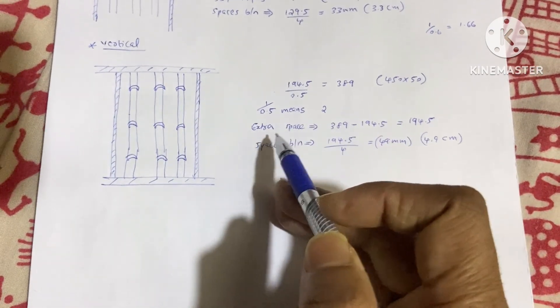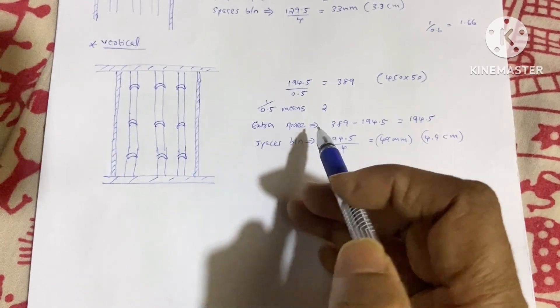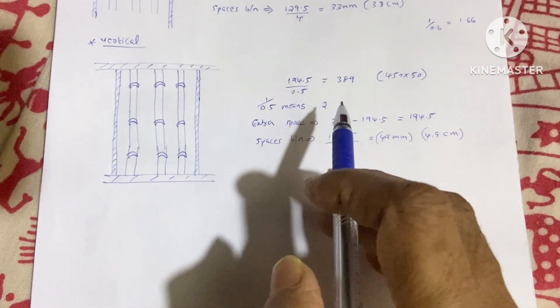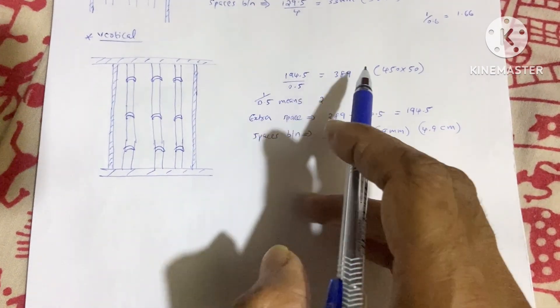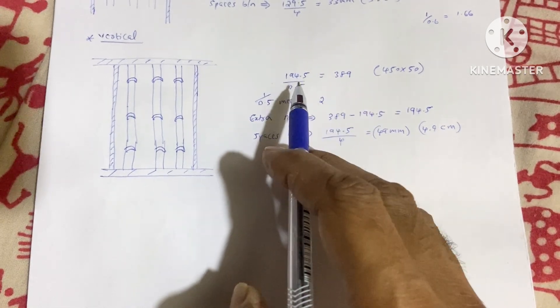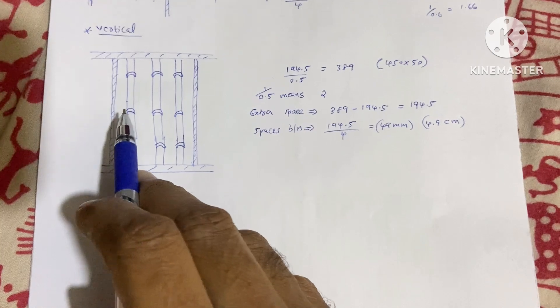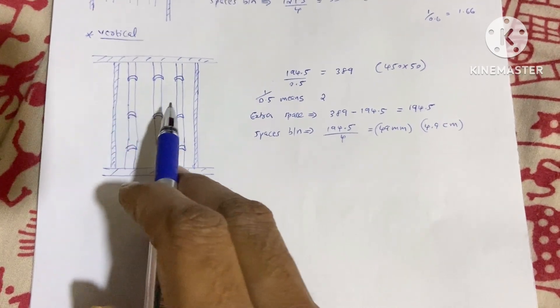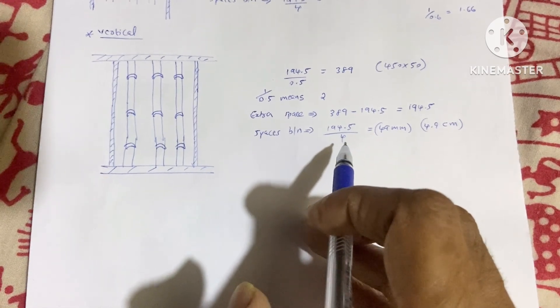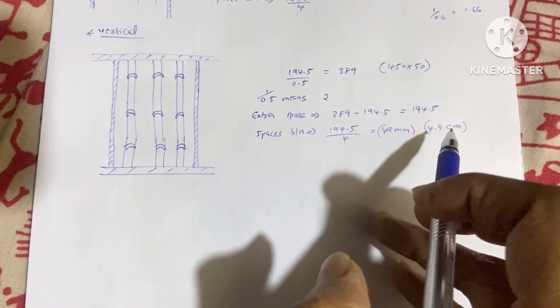The extra space available in the vertical calculation is the difference between 389mm and 194.5mm, which equals 194.5mm. With 4 gaps present, dividing 194.5mm by 4 gives 49mm — that is 4.9cm of spacing per gap between cables and cable tray.